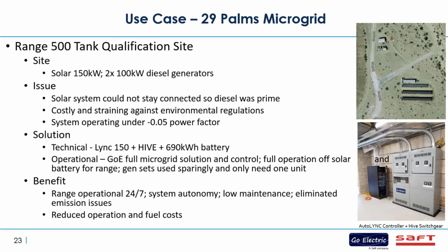What we found was very intriguing. Alex can walk through some of the technical aspects of the limitations, but they have a 15 kV system that controls the targets, and that's a buried system. So it's not above ground, which all of a sudden gives you a very high impedance situation. On top of that, the operating power factor was negative 0.05, which is hard to come by. That had everybody scratching their head.